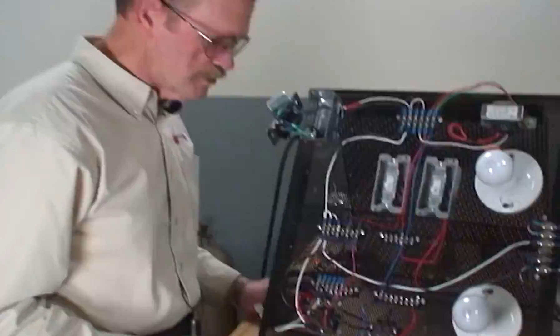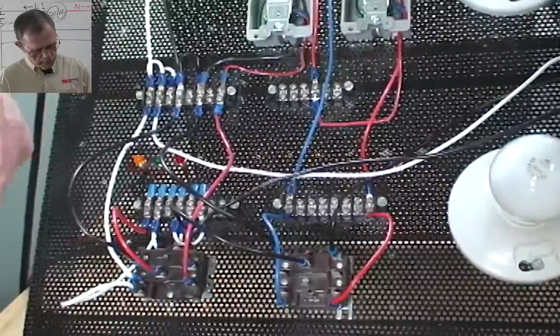Now, what does the relay do itself? That's the one we haven't finished off yet. We've got two switches here: a normally closed switch that goes from here to there, and a normally open switch that goes from here to there. This wire right here feeds both of those switches, one normally open, one normally closed. But where does this wire come from? Well, once again, it's L1, because L1 here goes back to the fuse. So it parallels off, came down here, paralleled over, comes to here.